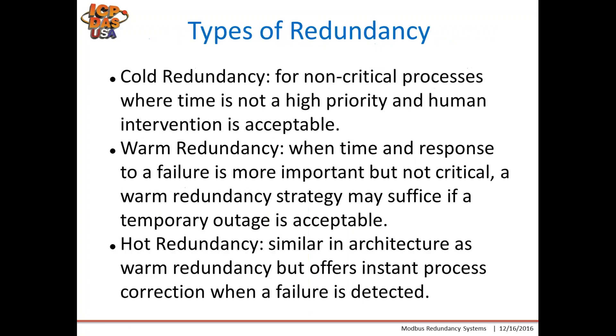There are three types of redundancy. Cold redundancy is for non-critical processes where time is not a high priority and human intervention is acceptable. As an example, if a press machine fails, the automation system should notify the operator and issue an alarm. A simple response may be to cut the power to the power supply and display a red alarm light. The operator can resume operation by simply starting another unit and requesting service for the failing unit.